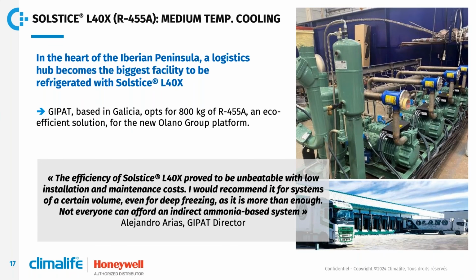The second case study, here we have a logistics platform in the south of Europe, also choosing R455A for medium temperature. In this example, in fact, the space classification and the system location are not subject to load restrictions, allowing, consequently, an installation in direct expansion using about 800 kg of charge. Again, here, the motivation of the end user was both low installation cost and low maintenance cost compared to ammonia.